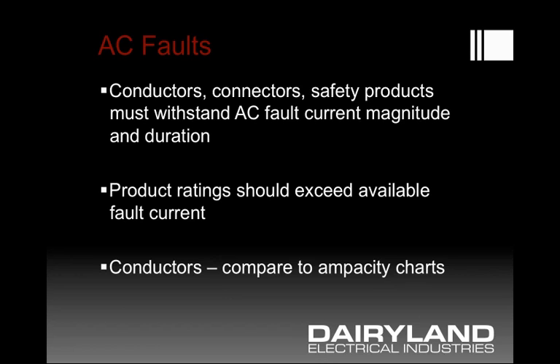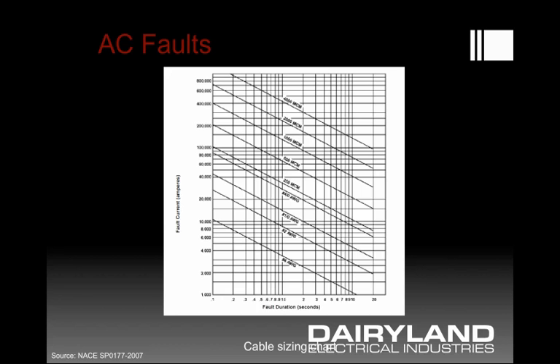Product ratings can be determined from manufacturer data, and conductor ratings can be determined from ampacity charts. Here's an example of conductor fault current withstand rating. You see current graphed on the vertical axis against time on the horizontal axis, with different conductors shown for the descending sloped lines. For different current-time combinations you can determine whether a particular conductor would be suitable for that task. Obviously the larger conductors can handle higher fault currents, so one merely sizes to coordinate that.